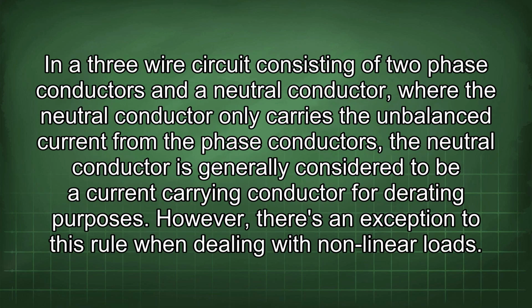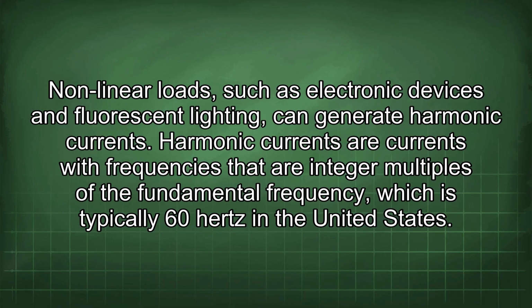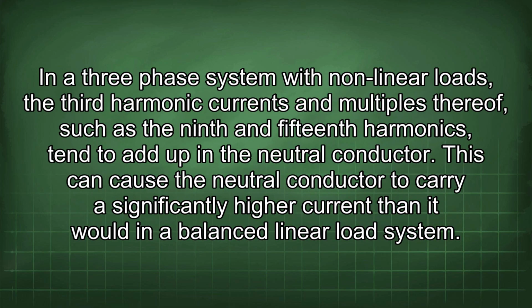In a three-wire circuit consisting of two-phase conductors and a neutral conductor, where the neutral conductor only carries the imbalanced current from the phase conductors, the neutral conductor is generally considered to be a current-carrying conductor for derating purposes. However, there's an exception to this rule when dealing with nonlinear loads. Nonlinear loads, such as electronic devices and fluorescent lighting, can generate harmonic currents. Harmonic currents are currents with frequencies that are integer multiples of the fundamental frequency, which is typically 60 Hz in the United States. In a three-phase system with nonlinear loads, the third harmonic currents and multiples thereof, such as the 9th and 15th harmonics, tend to add up in the neutral conductor.